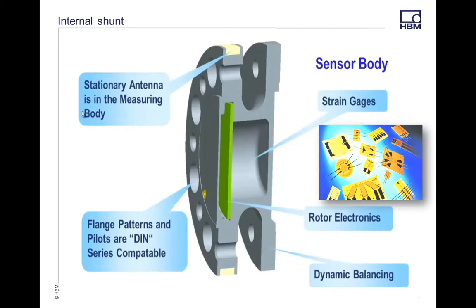On ours, it's on the interior of this machined pocket. So as it spins, it's getting pushed inside of the metal instead of being pushed off and pulled off. This increases our accuracy and our linearity and hysteresis as the rotor spins.